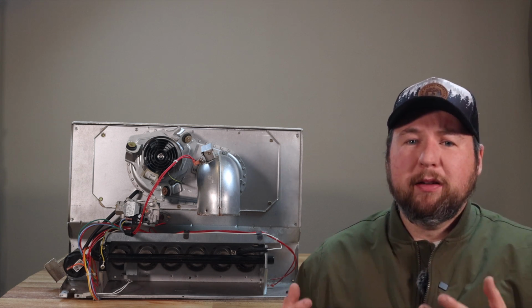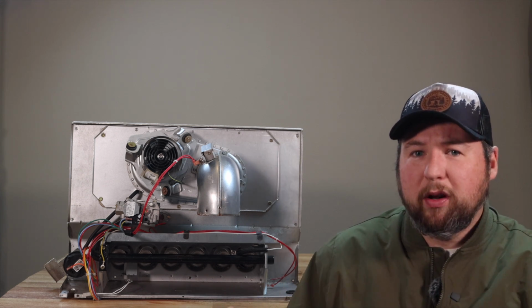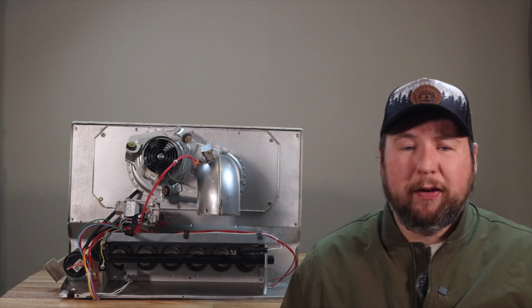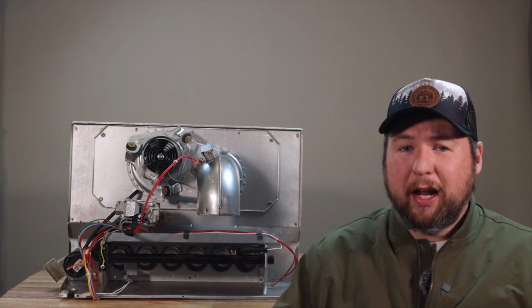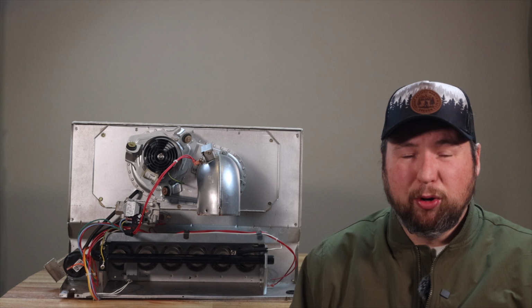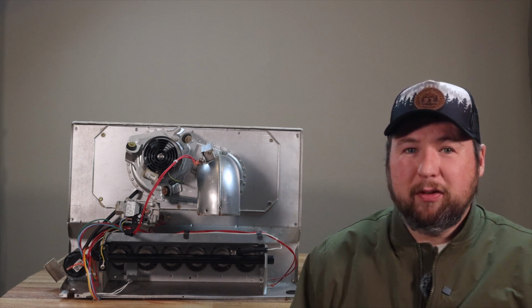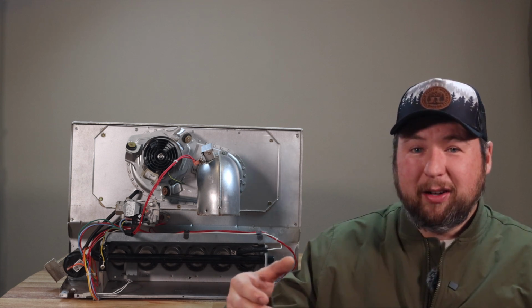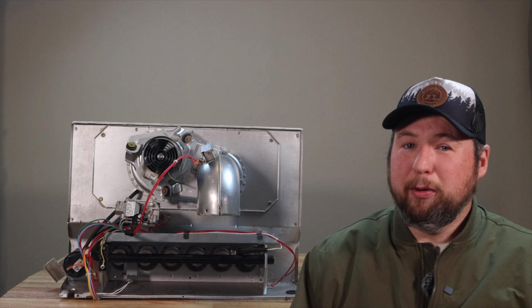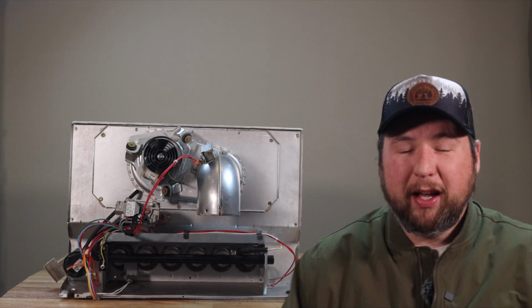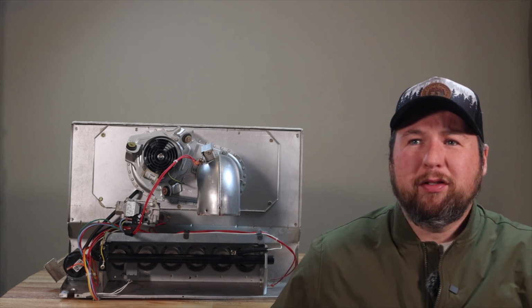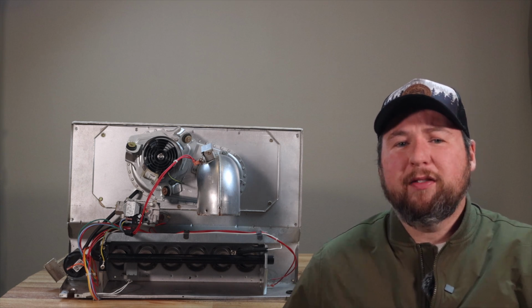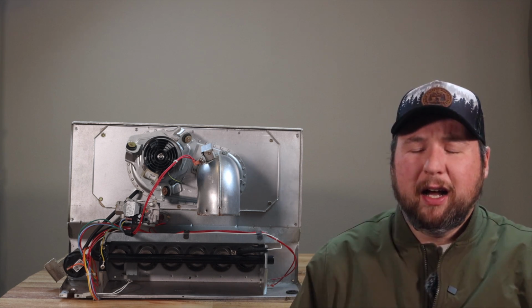And the reason why is because it was a great insulator. So if it touched any wood, you didn't have to worry about it getting so hot it would cause a fire, because that exhaust off of a natural draft furnace, that temperature, it's really high. So be careful if you see one of those. If you see like a single wall hooked up to that, don't touch it, because it will burn you. Those things get really hot. I forget exactly what the average temperatures for the exhaust for those are, but they're pretty high.